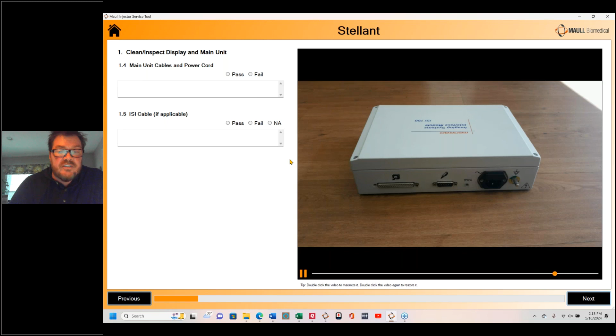Now, this isn't a model specific thing. This is true of every contrast injector, and this is what I talk about with all the students. The cleaning portion of a PM on a contrast injector is a kind of a wild card, a variable. How much cleaning is necessary on a contrast injector can dramatically increase the length of time you're going to spend doing on this PM. But one of the things the manufacturers are adamant about is no cleaning solvents are necessary, water only. Contrast injectors use contrast and saline to do what they do.